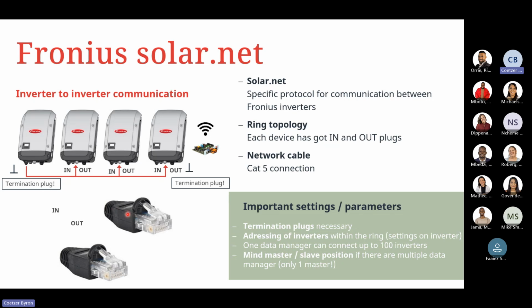So again, making sure that we have our end of line termination plugs on the outside of the units, both the last slave and the master will have one of the RS-485 RJ45 end of line connection blocks. So there are important settings and parameters when you are using SolarNet. Make sure that the termination plugs are correctly installed. The addressing of the inverters is very important. So we need to make sure that we start the master at 01 and the first slave is then 02, for example, and then following on as such.